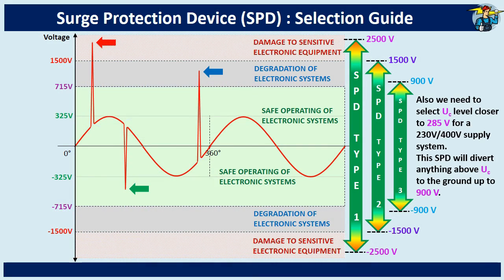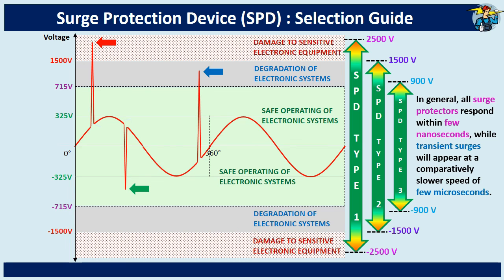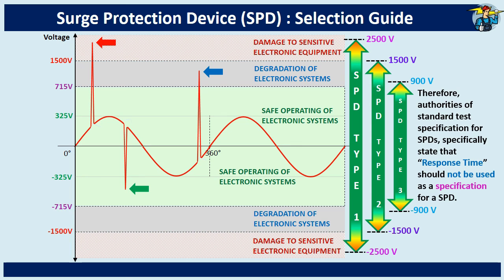Further, we need to select a UC level closer to 285 volts for a 230 volt or 400 volt supply system. This SPD will divert anything above UC value to the ground, up to 900 volts. That means if this SPD receives a 900 volt transient surge, it will allow 285 volts to the load side, and will divert the balance 615 volts to the ground within a few nanoseconds. In general, all surge protectors respond within a few nanoseconds, while transient surges appear at a comparatively slower speed of a few microseconds. Therefore, standard test specifications for SPDs specifically state that response time should not be used as a specification for an SPD.